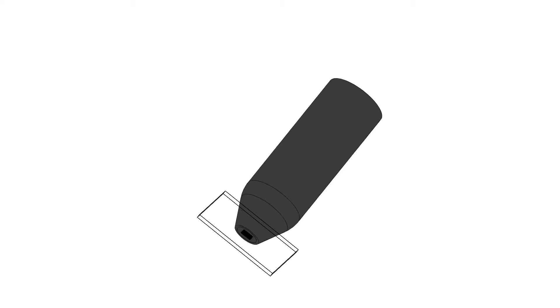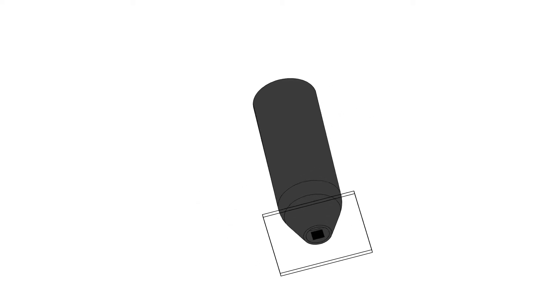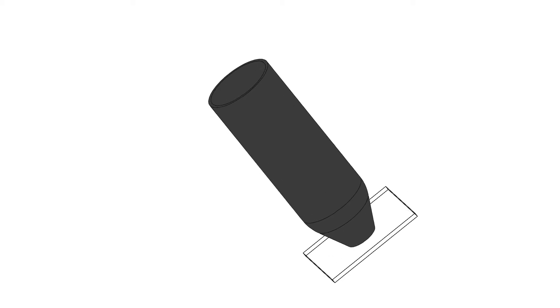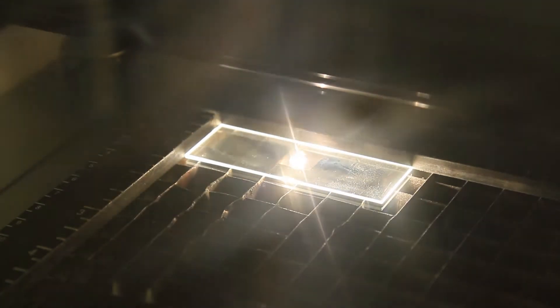We designed an inexpensive, modified cuvette for selective capture of CTCs from whole blood. We prototyped the cuvette using 3D printing and laser etched our imaging surface to enable enumeration of captured cells.